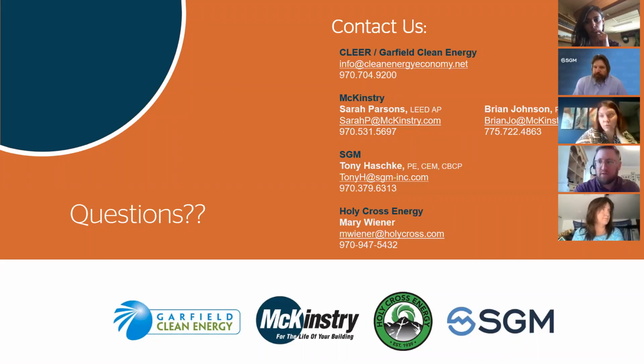Okay. Yeah, Tony, the winter temperatures in heating dominant climates have been one of the limiting factors when we've assessed HVAC systems. ASHRAE may recommend 100% outside air. That's absolutely not going to work in a heating dominant climate in the middle of winter. So we actually look at leaving air temperatures at an increased ventilation set point and making sure we still have the capacity to heat the building. And it's also a challenge during that pre-occupancy flush. Normally you close dampers and recirculate, giving maximum capacity.